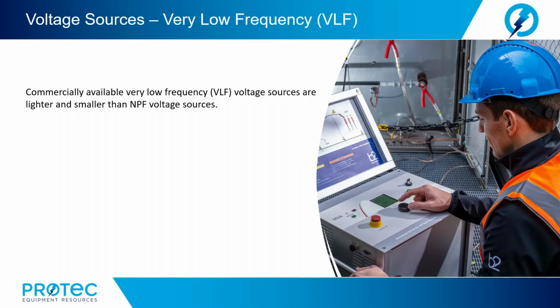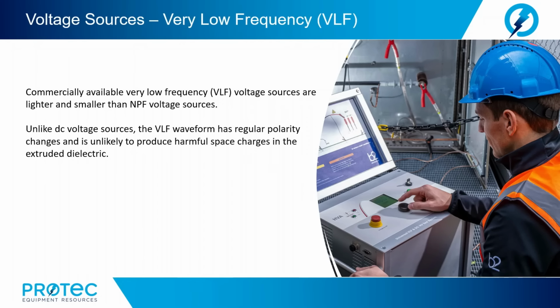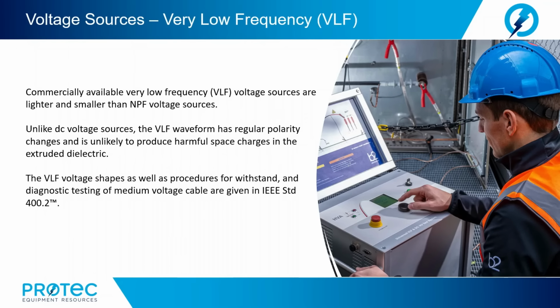Now, commercially available very low frequency voltage sources obviously are now lighter and smaller than their near power frequency counterparts. Unlike DC voltage sources, the VLF waveform has regular polarity changes and is unlikely to produce harmful space charges in the extruded dielectric, which is a problem that is given to us in DC testing. Now, the VLF voltage shapes, as well as the procedures for withstand and diagnostic testing of medium voltage cable, are well documented and given in the IEEE standard 400.2. VLF-based testing is also given in the NETA testing specifications.